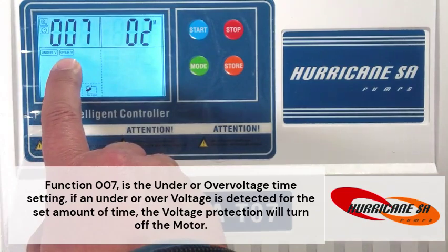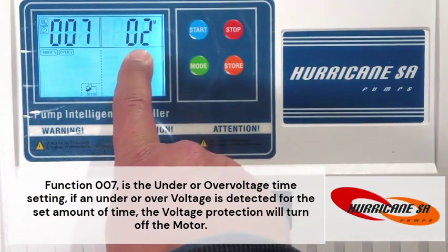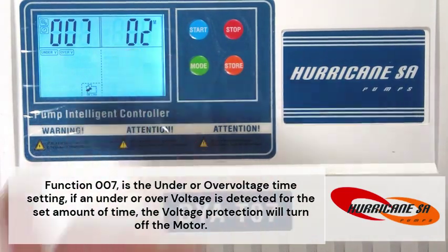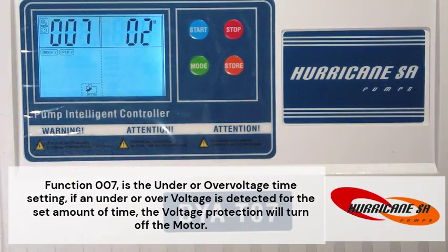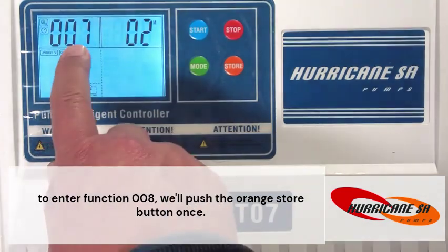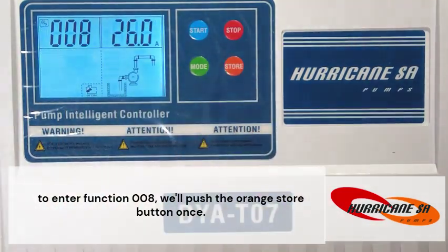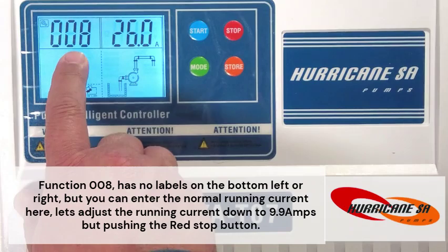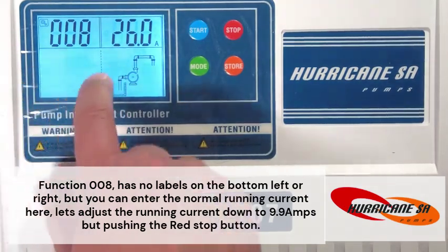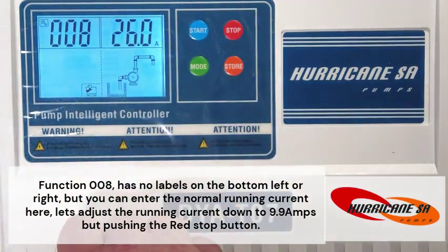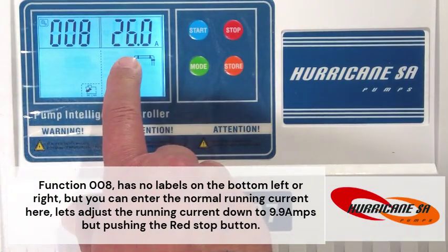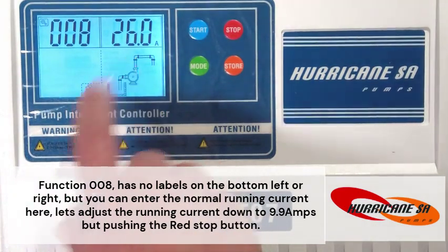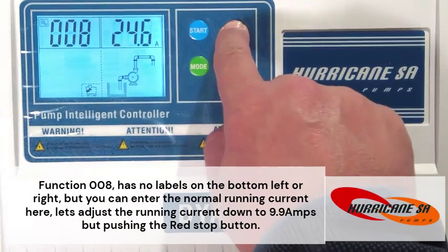Function 007 is the under or over voltage time setting. If an under or over voltage is detected for the set amount of time, the voltage protection will turn off the motor. To enter function 008, we'll push the orange store button once. Function 008 has no labels on the bottom left or right, but you can enter the normal running current here. Let's adjust the running current down to 9.9 amps, by pushing the red stop button.